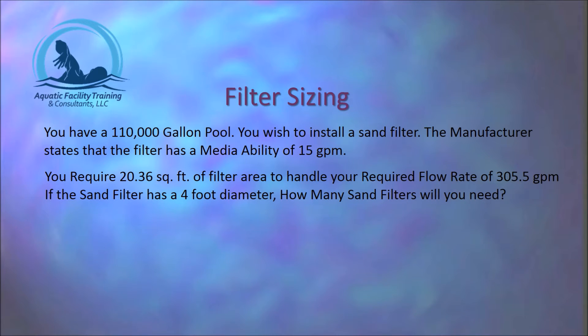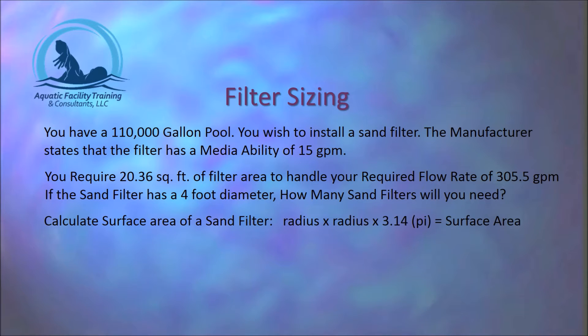Same pool — 110,000 gallons. Installing a sand filter, we require 20.36 square feet of filter area to handle our 305.5 gallon per minute flow rate. The sand filter we are interested in installing has a 4-foot diameter. How many sand filters must we install in order to handle that flow rate? First, we calculate the surface area of the sand filter using the formula pi r squared — radius times radius times pi, which is 3.14.